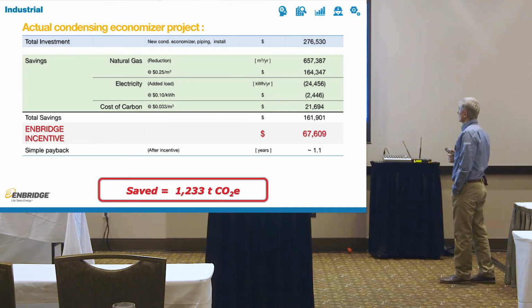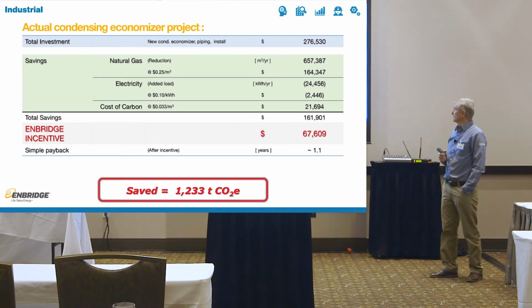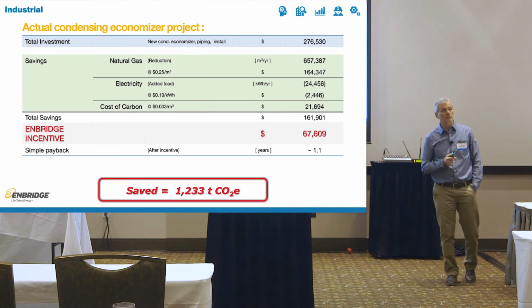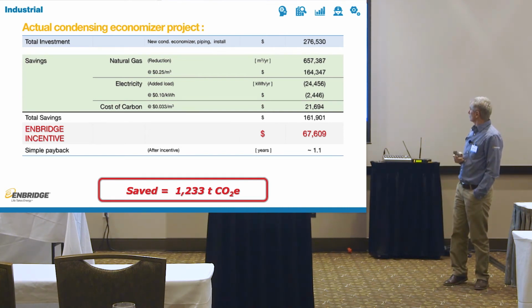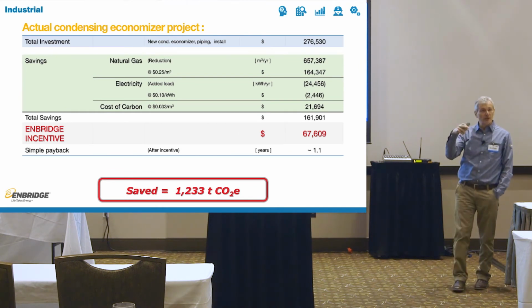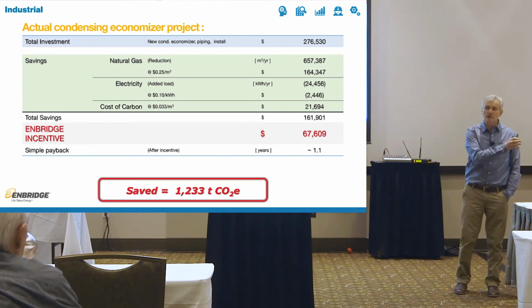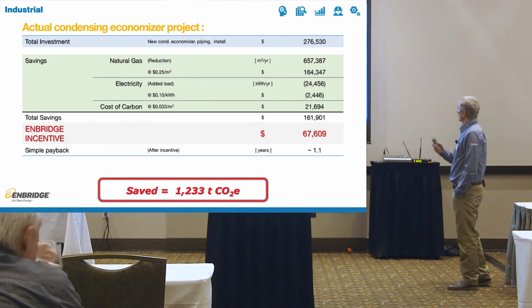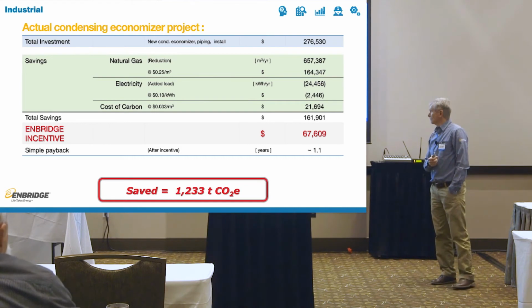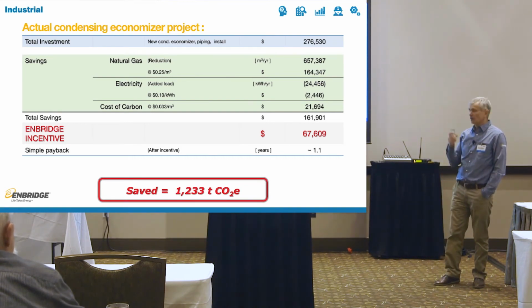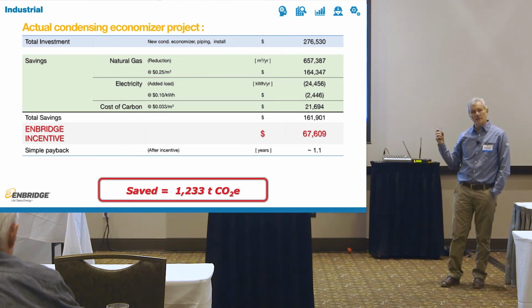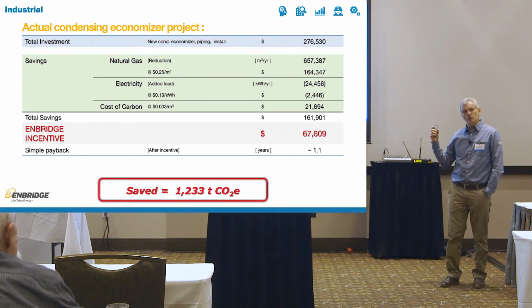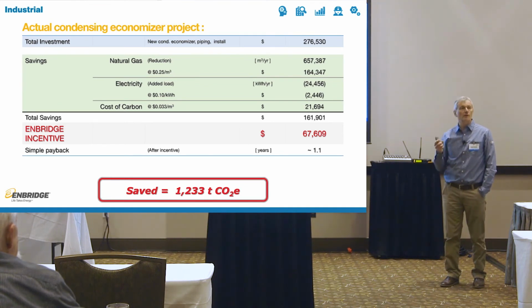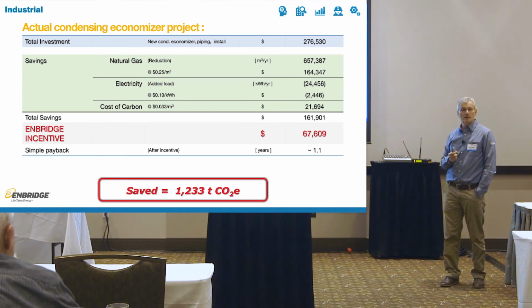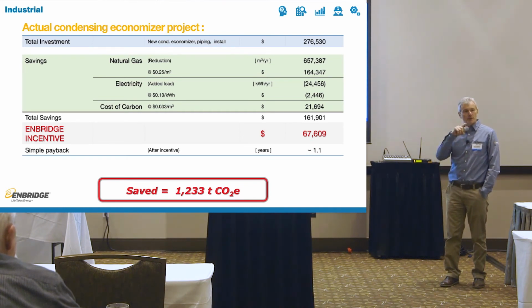They invested $276,000, which is not a small amount of money, but they saved 700,000 cubic meters of natural gas. They added a little bit of electricity load because you need a fan for the condensing economizer because it was one of those off-the-stack installations. But they still saved $162,000. We gave them $67,000 in incentives for about a 1 year payback. That facility now actually runs the most energy efficient facility in their global network because of a project like that. This reduced their KPI, energy per widget made, by about 40%.